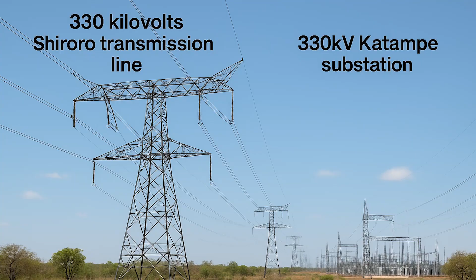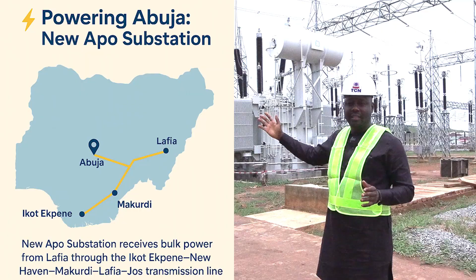The substation has a 2x150 MVA auto transformer, 330/132/33, which would have a 240 megawatt capacity, which will be added to the grid. In addition, this station is going to be powered by a 330 kV double circuit line from Lafia substation, Nasarawa State. This transmission line is about 143 kilometers. At present, it's about 85% completed. However, there are right-of-way and compensation issues which TCN management is currently addressing.